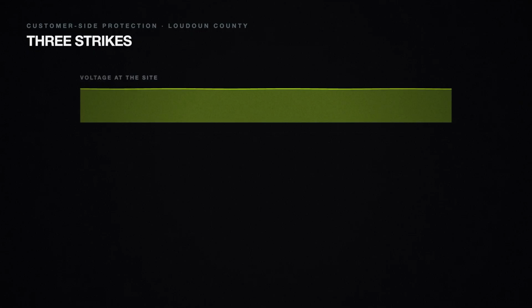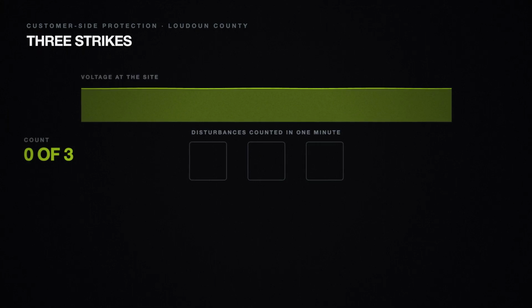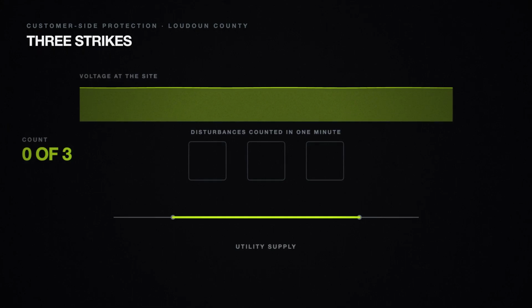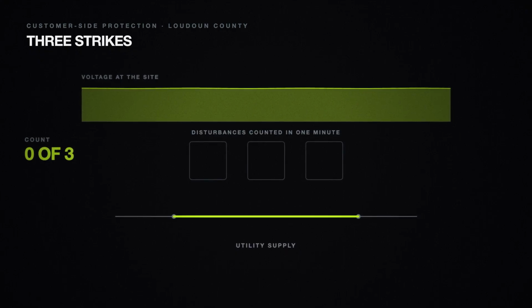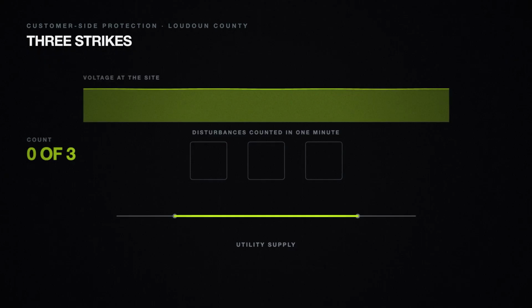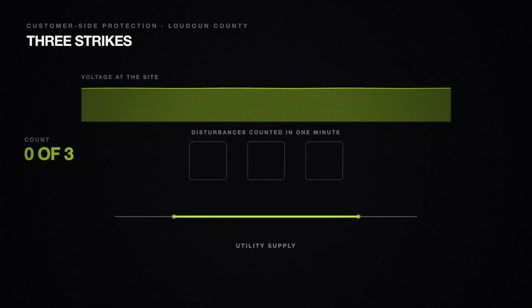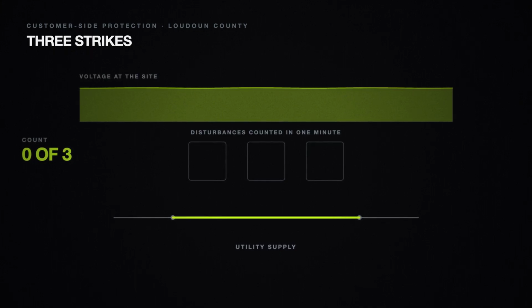Why did they leave? Not because anything reached them. The faults were 230 kilovolt events on the transmission system, cleared in a 20th of a second. What reached the data centers was a voltage sag. The lights dipped. A facility that cannot tolerate a dip installs protection that watches for it. And a common design does not simply watch, it counts. 3 disturbances inside 1 minute, and the scheme decides the utility supply is unreliable. It transfers the facility to its own backup, and it stays there. Not for a second, not until the voltage recovers, until a human comes and puts it back.